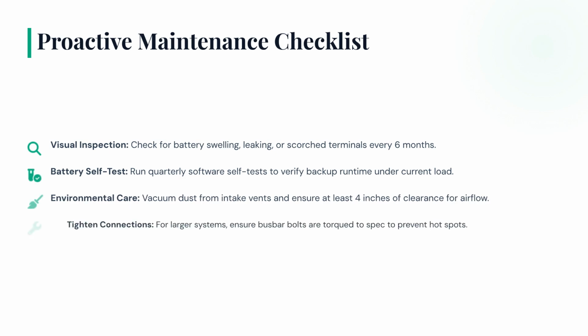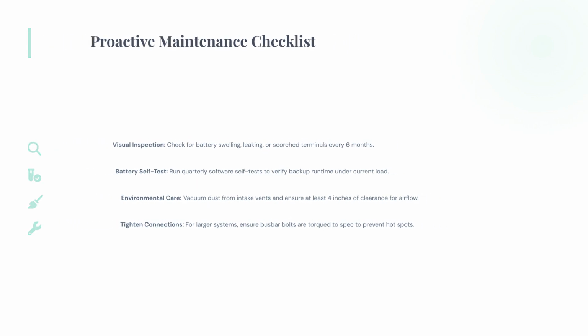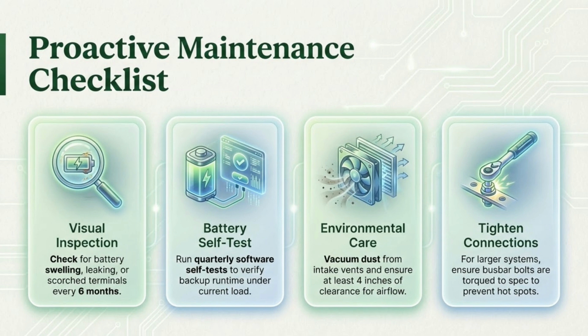Proactive maintenance includes a visual inspection every 6 months for battery swelling. Run quarterly software self-tests. Vacuum dust from intake vents. For larger systems, tighten connections to prevent hotspots. Following this checklist will help ensure your UPS system remains operational and dependable when you need it most.